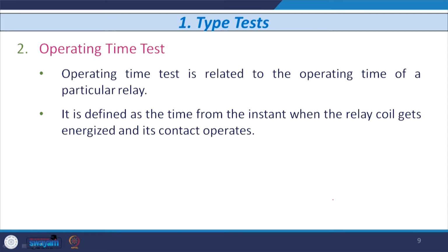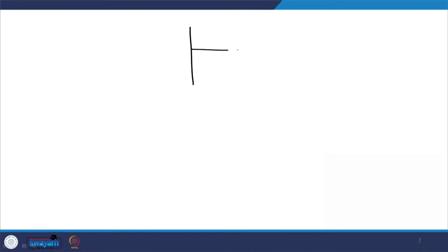Let us consider the second one, that is the operating time test. This is also one of the type tests that is to be performed by the manufacturer. The operating time test is related to the operating time of the relay. It is defined as the time from the instant when the relay coil gets energized to the time when the contact of the relay separates. Let me just tell you how this is done. Say we have the relay that is located here.